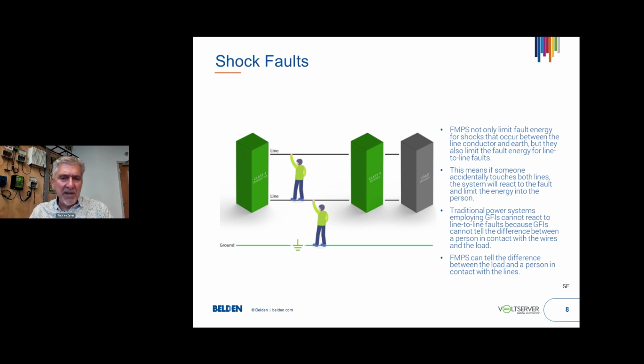And I should point out that conventional systems up to this point have not been able to detect line-to-line faults. Many of you might be familiar with ground fault interrupters, but remember that those are protecting from a fault from a line connection to earth. Like in the lower part of the drawing where the little person's feet are on a ground plane and their hand is on one of the line conductors. Currently, there's no known technology that can detect that kind of fault and respond to it in any way that provides the level of safety needed for certification.